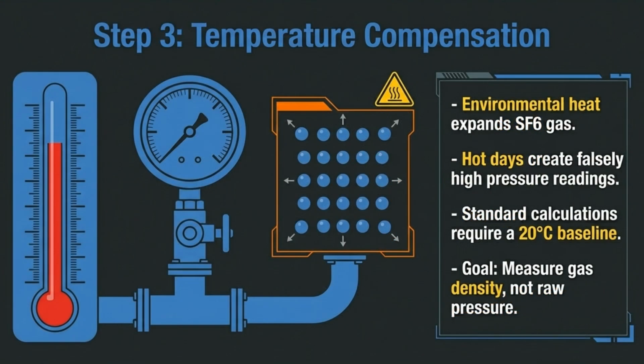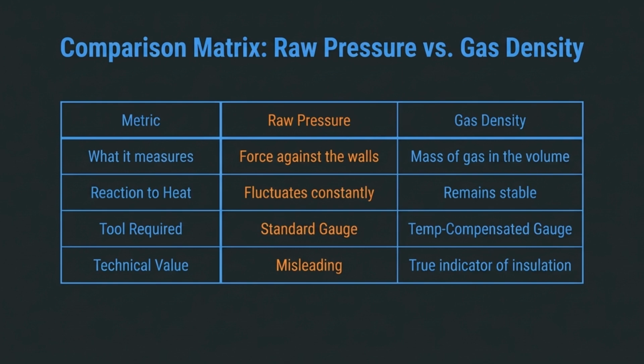Step 3 is temperature compensation. Environmental heat expands the gas, creating falsely high pressure readings. The goal is to measure gas density, not raw pressure, using a 20 degrees Celsius baseline. Raw pressure is misleading because it constantly fluctuates with heat. Gas density, measured with a temp-compensated gauge, is a stable, true indicator of insulation integrity.